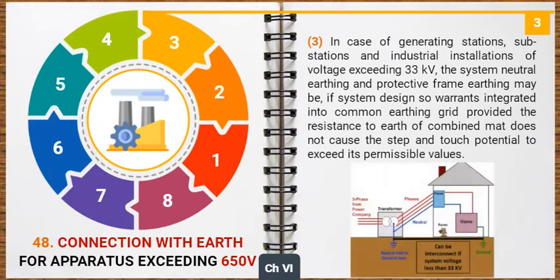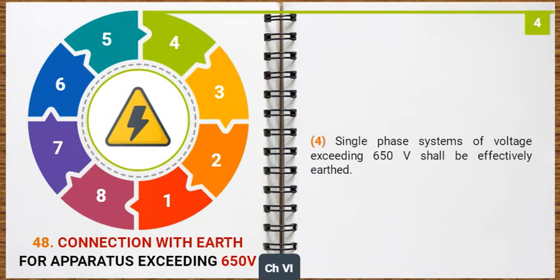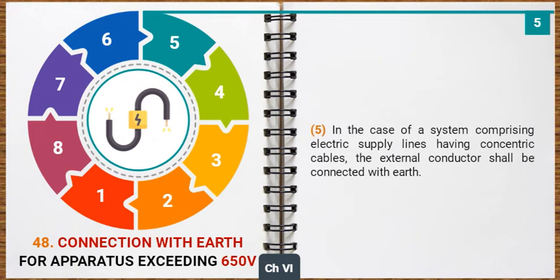In case of generating stations, substations and industrial installations of voltage exceeding 33 kV, the system neutral earthing and protective frame earthing may be, if system design so warrants, integrated into common earthing grid, provided the resistance to earth of combined mat does not cause the step and touch potential to exceed its permissible values. Single-phase systems of voltage exceeding 650 volt shall be effectively earthed. In the case of a system comprising electric supply lines having concentric cables, the external conductor shall be connected with earth.